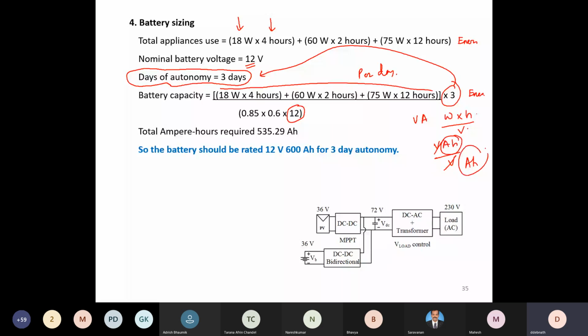But there are two other important factors I've considered, as you can see. One is 0.6, which is the depth of discharge. If you have a 100 ampere hour battery, you might assume it gives you 100 ampere hour throughout, but for a lead acid battery, depth of discharge is usually around 20 to 40% of state of charge — once it drops to around 40%, we generally don't drain it further, to increase the life of the battery. For a lithium ion battery, you can go down to around 20%.